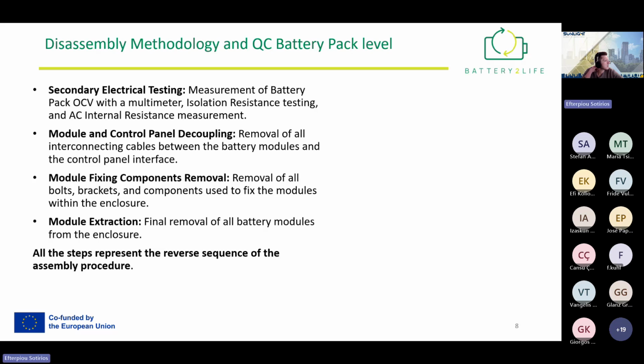After module and control panel decoupling, we remove all interconnecting cables between the battery modules and the control panel interface, and remove the bolts, brackets, and components used to fix the modules within the enclosure. The final step at battery level is module extraction, removing the modules from the enclosure. All these steps represent the reverse sequence of the assembly procedure, so it's a kind of reverse engineering.